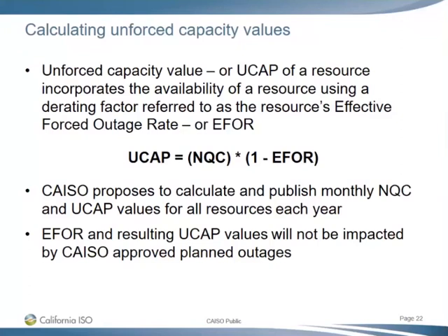Well, let's say you have a frequency and then you convert that frequency to probability. Then you say, okay, this unit has a 95% chance of operating at its full capacity, but there is a 5% chance that this unit may have a derate. It could be a complete derate, it could be a partial derate. But then you multiply this 95% with the full capacity value, and you say, this is my expected value in terms of megawatts. I don't think that's automatic.